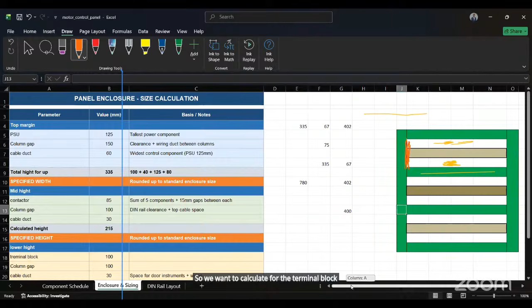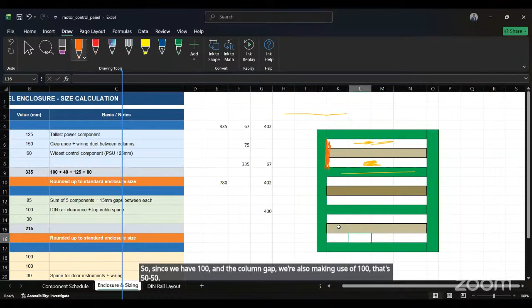We've calculated from this top part to this part now. So we want to calculate for the terminal block, 100 in the middle. Since we have 100, the column gap also makes use of 100 — that's 50, 50. So the terminal block in the middle is 100, plus 50, 50, that's 200. Since we stopped at this place before, we'll add this 30 for the lower part, giving us 230.